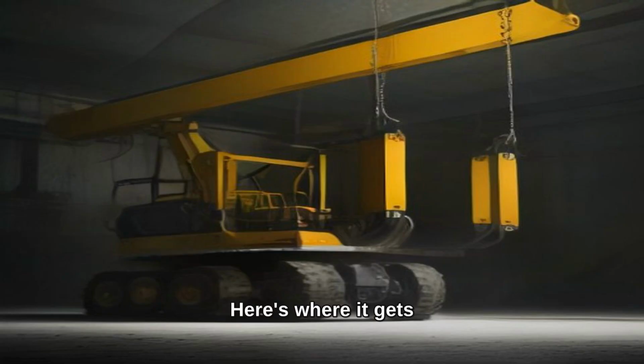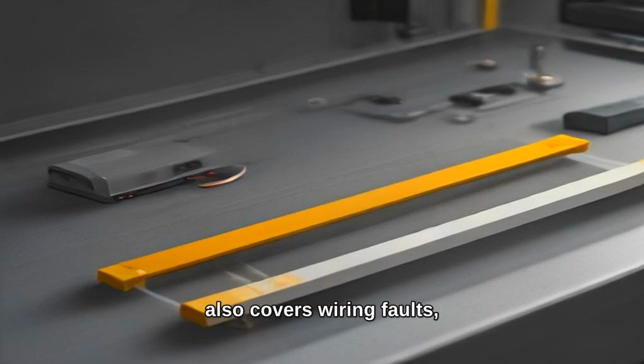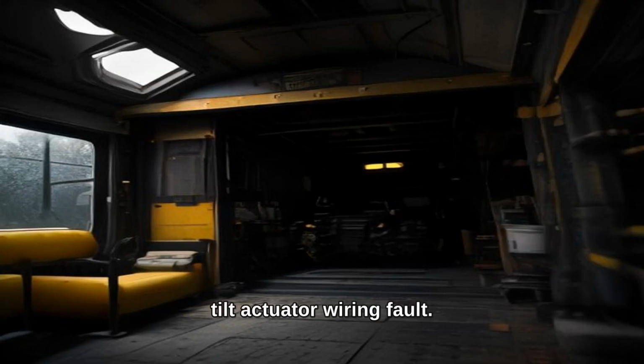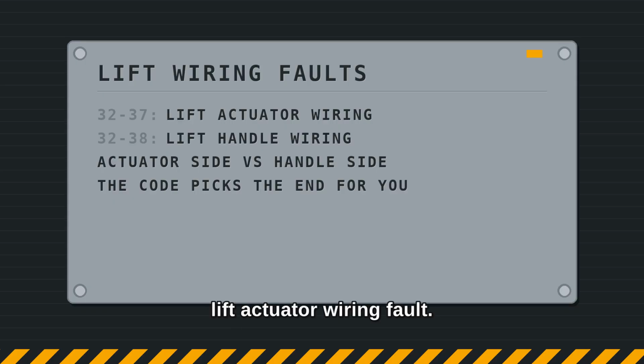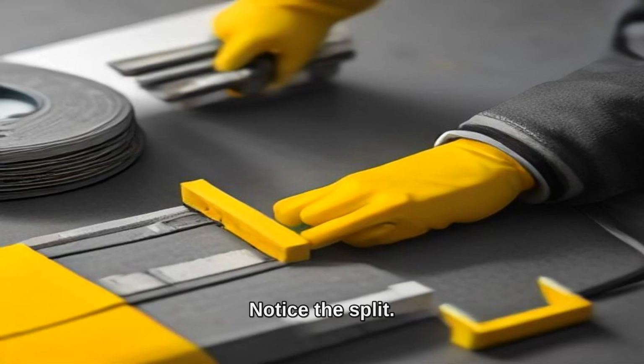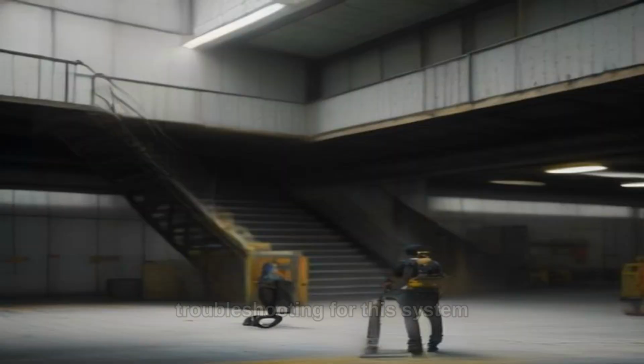Nothing to order. Here's where it gets more expensive and where guessing starts costing real money. The 32 family also covers wiring faults, and they're split by which end of the circuit is lying. 3232 is tilt actuator wiring fault. 3233 is tilt handle wiring fault. 3237 is lift actuator wiring fault. 3238 is lift handle wiring fault. Notice the split. The controller already separated the handle side from the actuator side. That's half your diagnosis, and the manual's own troubleshooting for this system starts nowhere near a parts counter.